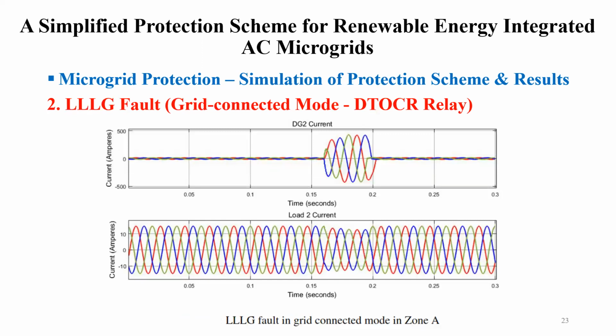Similarly, if we introduce a line to line to line ground fault in grid connected mode, this also shows the operation of our DTOC relay. We can see that at around 0.16 seconds, the fault is introduced. Here the load current starts to shift, and the current overshoots. As soon as the relay operates and trips and removes the faulted line, the grid comes back to its normal state of operation, again in less than 0.1 second.